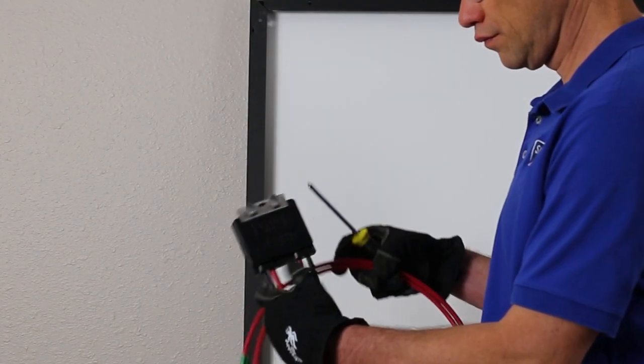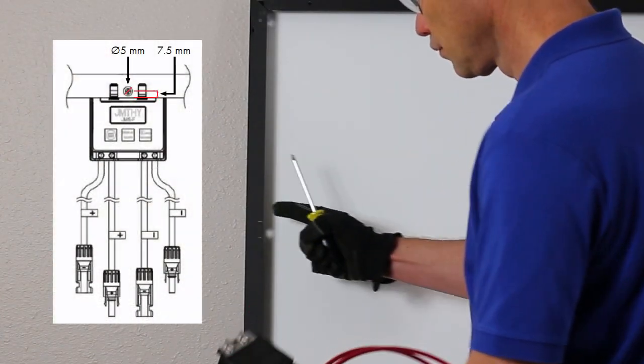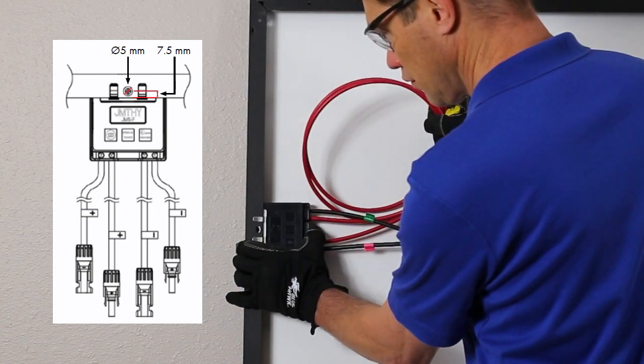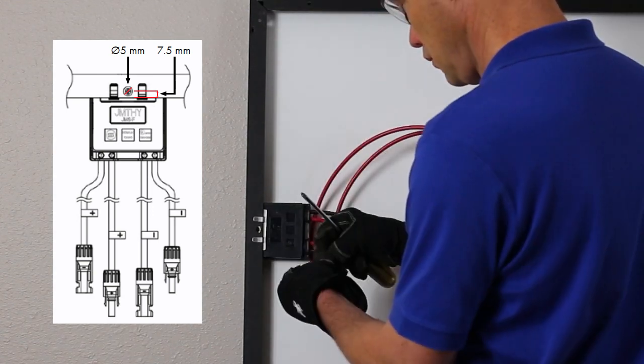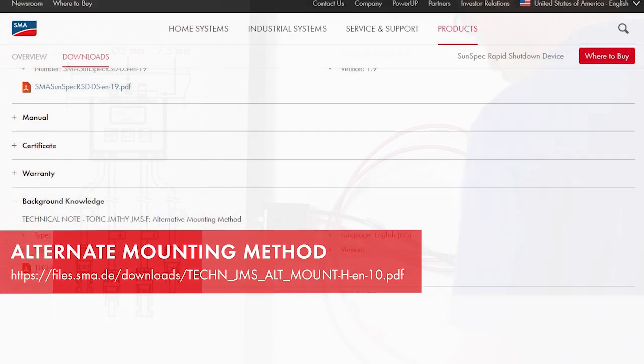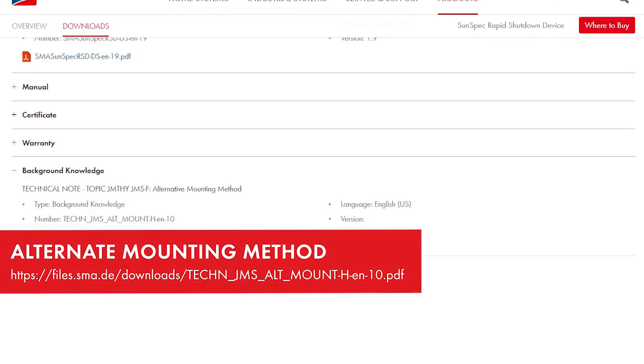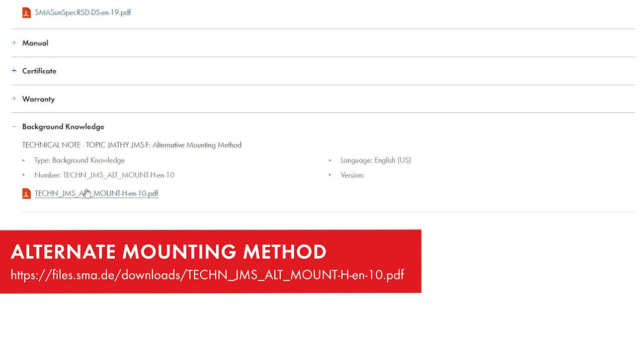Installation of this receiver utilizes a module frame mounting hole that is centered 7.5 millimeters from the frame lip. The device slides onto the module frame, and the included screw and washer are used to secure the device. If there is not an appropriate mounting hole available, please consult the SMA technical note for the alternate mounting method.